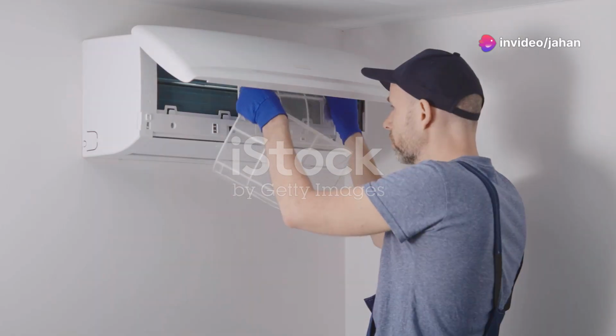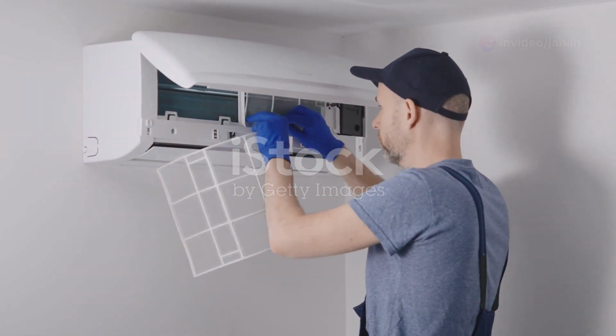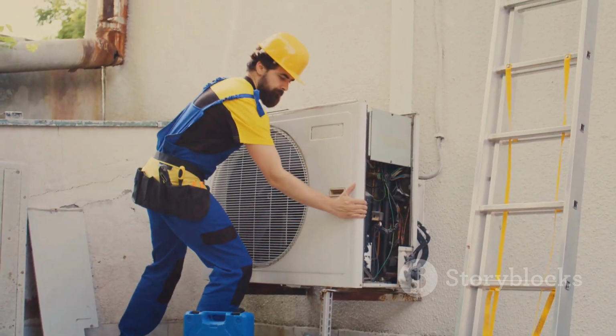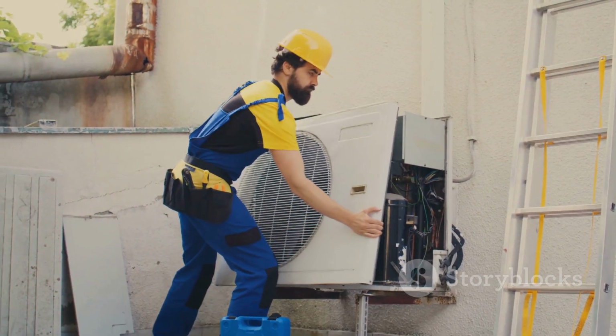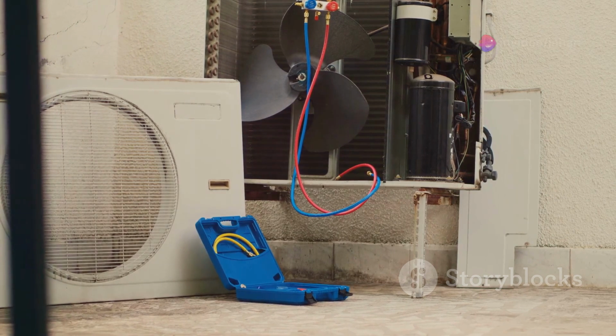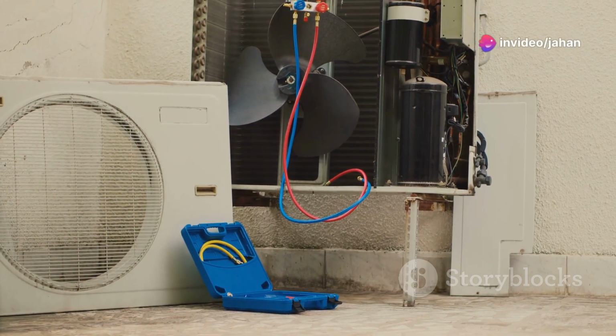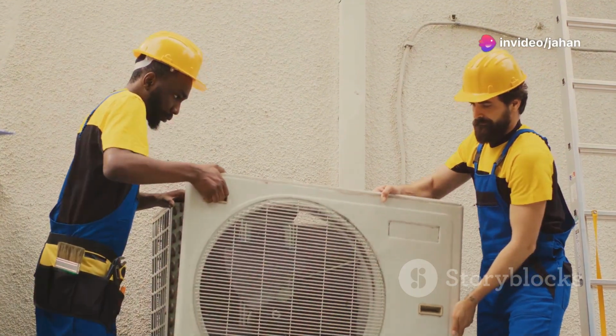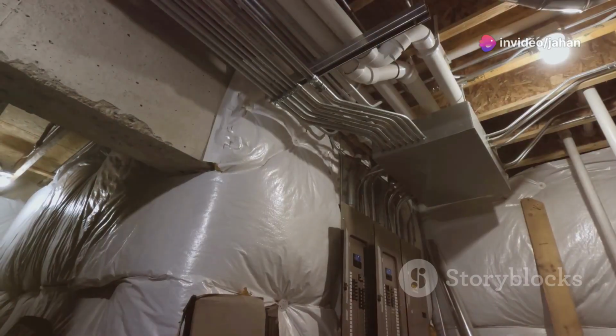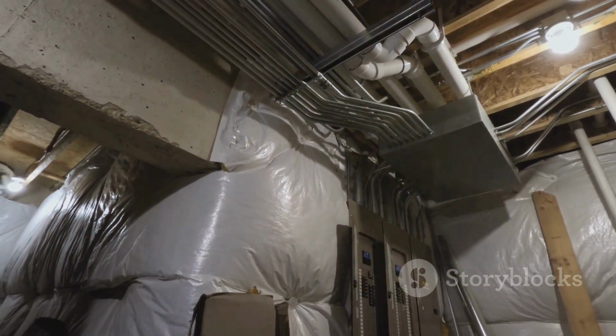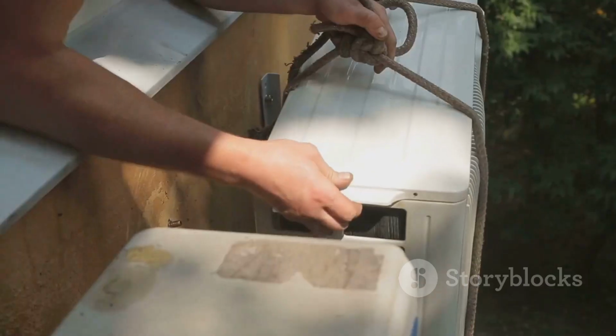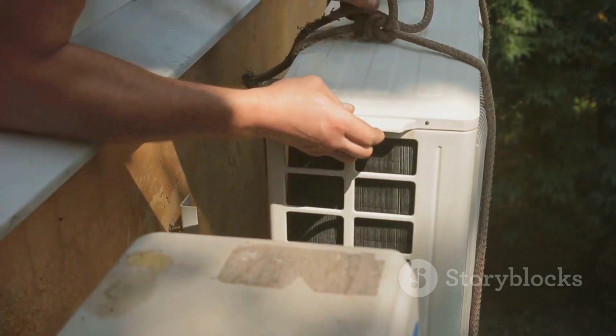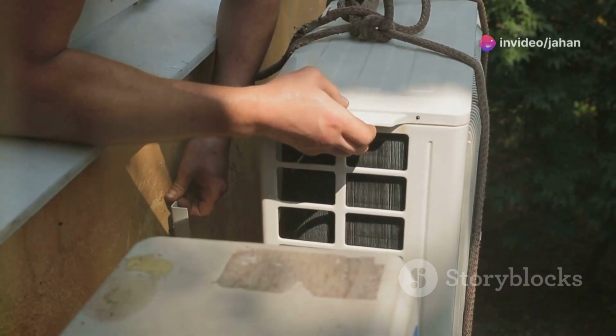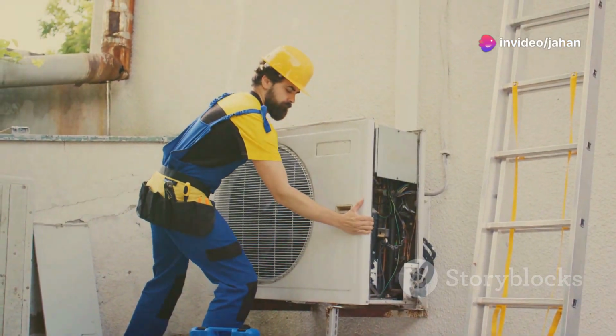Section 6. Outdoor operations. Mounting the muscle. Now, let's move outside and tackle the outdoor unit. This is the heart of your system, housing the compressor and condenser coil. Choose a level, solid surface for the unit. You might need a concrete pad or a mounting bracket depending on your setup. Secure the outdoor unit to the pad or bracket using bolts and washers. Make sure it's level and stable.